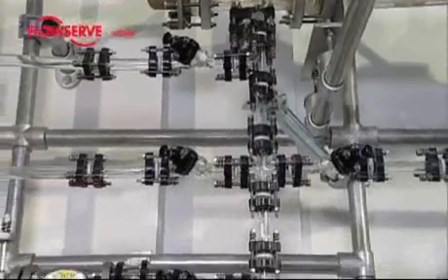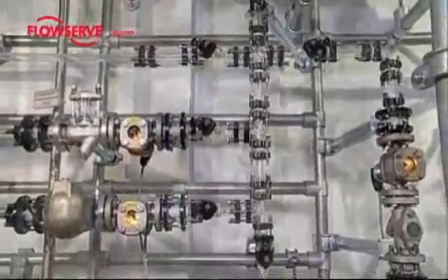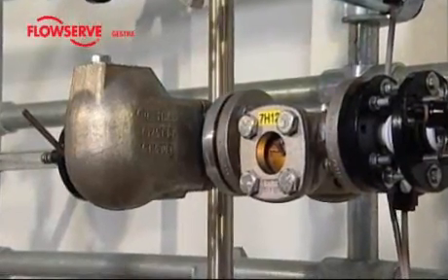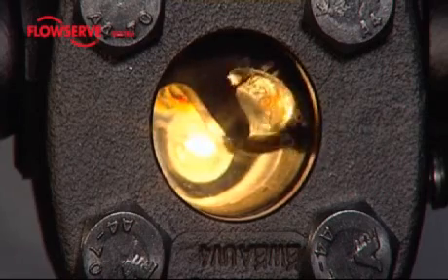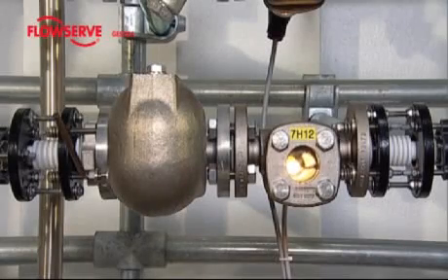The steam traps used for draining the heat exchanger are mounted below the heat exchanger. This video presents the ball float trap, type UNA-16. The float trap is preceded by a special sight glass, the Vaporscope VK-16, which is used for monitoring the steam traps and making the flow processes visible.